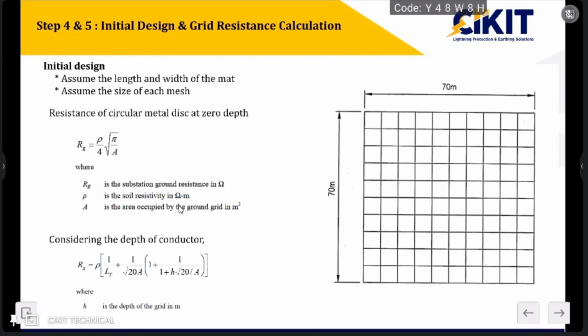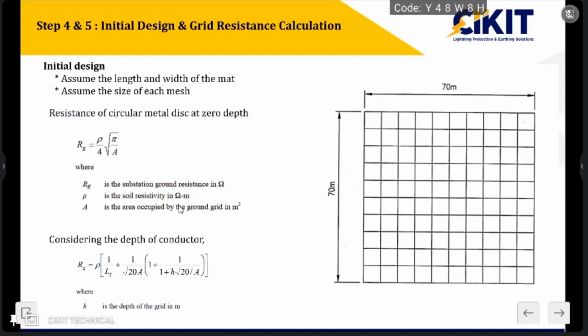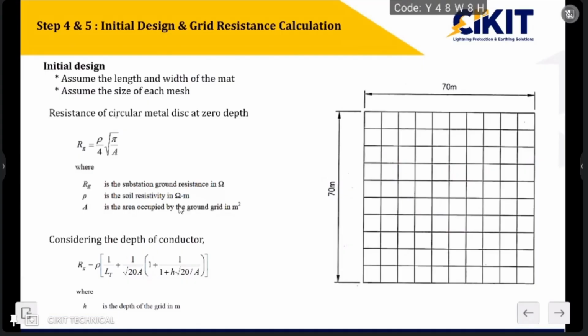So the next step is performing this initial design. The first step we can do, based upon the area availability, is to make a rough estimate. Like if the area is 70 by 70, we can go for the initial stage. We can have a mesh size of 5 meter cross 5 meter or 10 meter cross 10 meter. There is no regulation that I have to begin with 10 meter spacing or 5 meter spacing. So based upon the area availability and the soil resistivity value, initially we can go with this assumption. So let us try with 10 meter spacing.